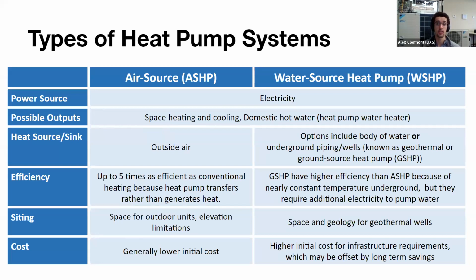The biggest difference is that air source heat pumps use air as the heat sink or heat source to reject or absorb heat. For water source, as the name implies, they use water, whether that's water from a gas-fired boiler loop or from geothermal. And when it's from geothermal, it's actually called ground source. In terms of efficiencies, we'll get into that in a little bit. On the air source side, they can be up to 5 times as efficient as conventional heating, as we previously mentioned, as they actually transfer heat. And on the water source side, they do tend to have slightly higher efficiencies than air source heat pumps, but they do require some additional pumps and some additional equipment on the water side.